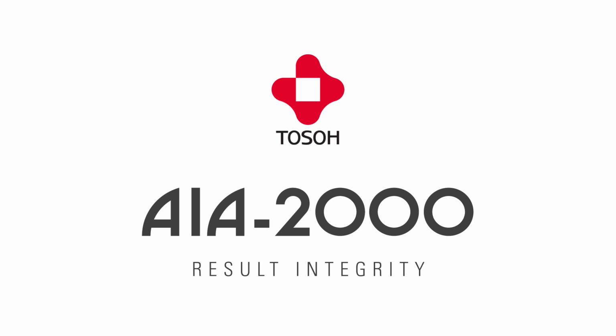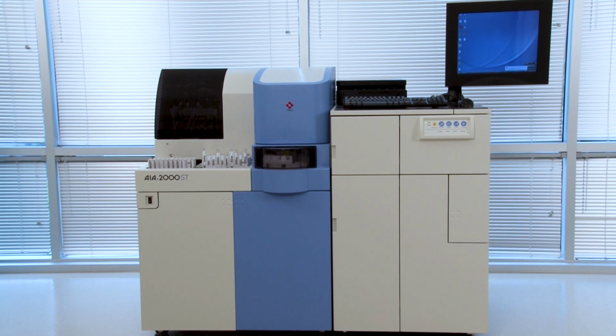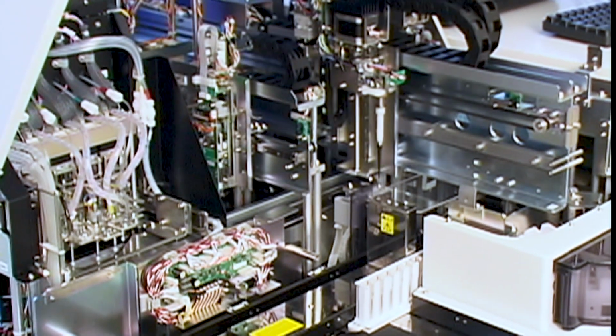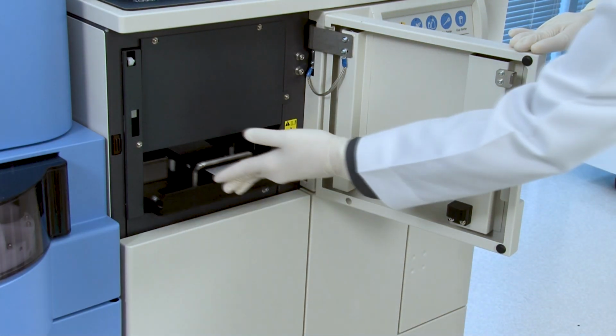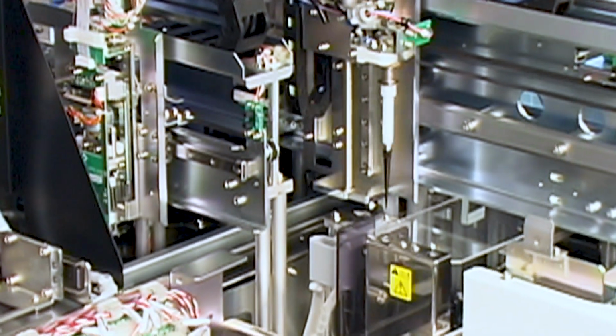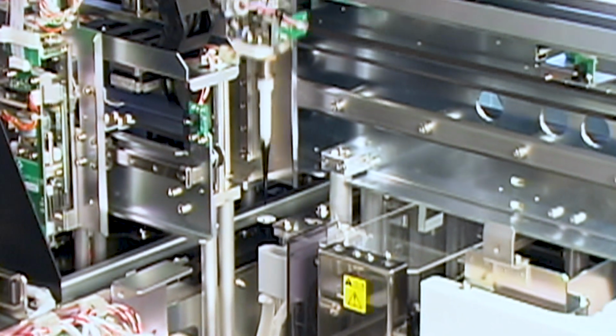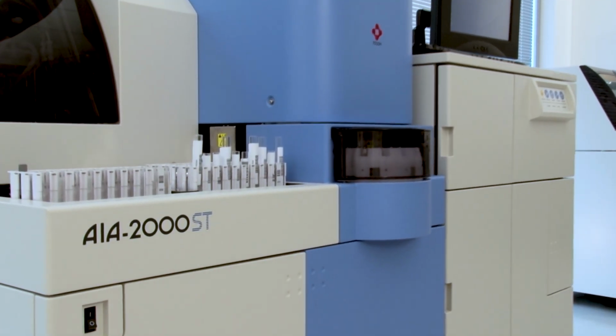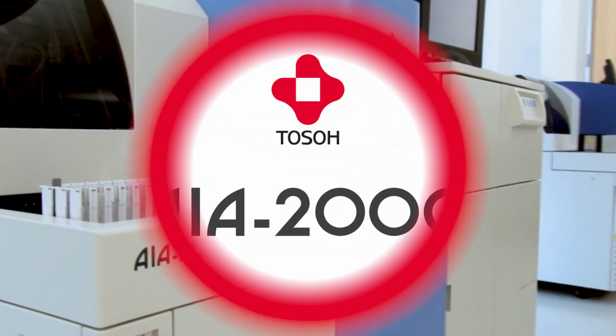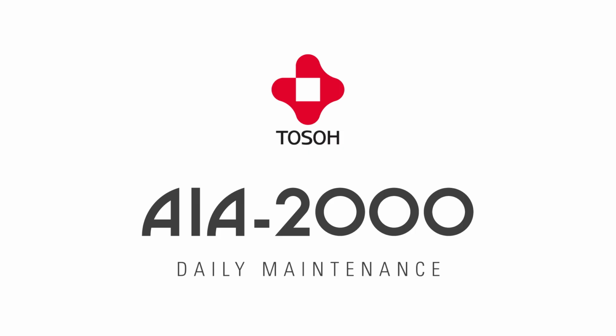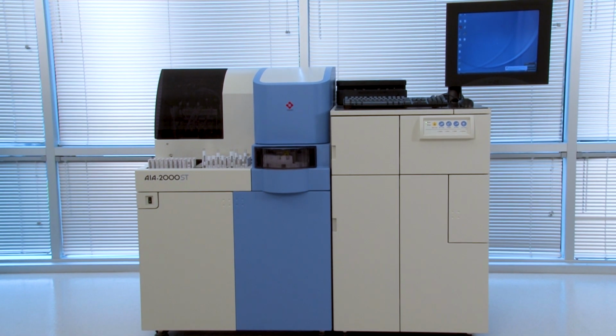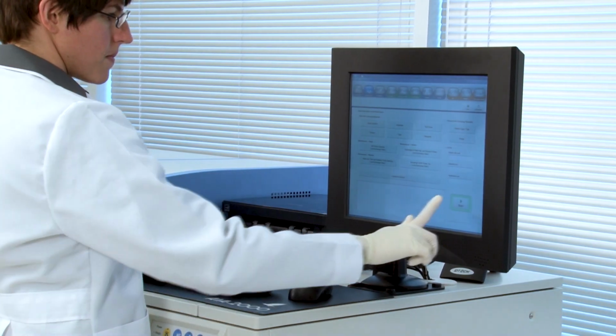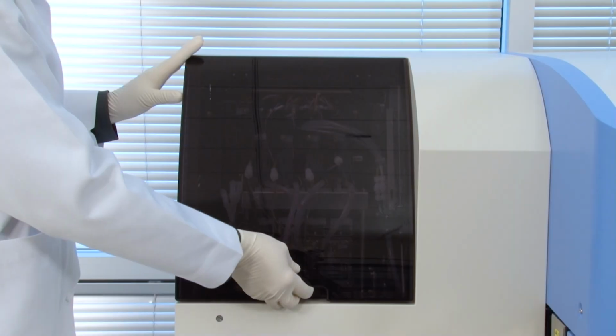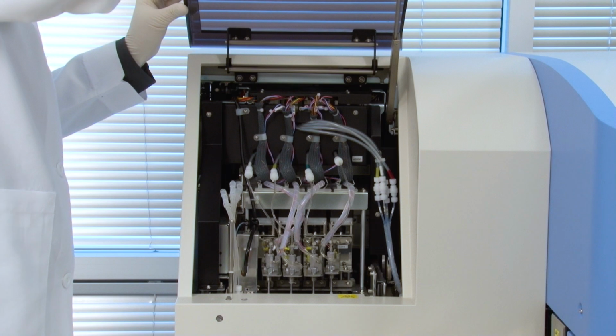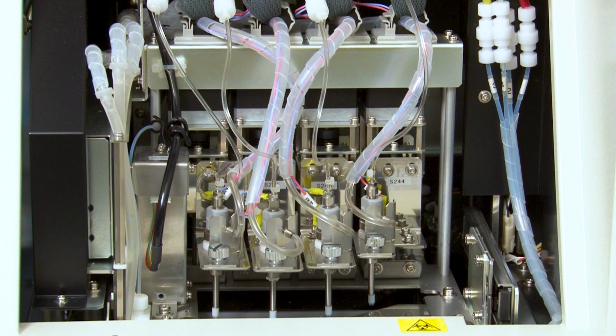To ensure the highest level of result integrity, the AIA 2000 features several built-in safeguards, including conductive disposable pipette tips for automated sample level sensing and elimination of carryover. The system also features TOSO's exclusive clot detection, which will detect a clot at the beginning of the sample processing and again during the wash phase. Daily maintenance on the AIA 2000 is totally automated and requires only 5 minutes per day at system startup. Weekly maintenance requires only a few minutes of operator time and involves a simple cleaning of the wash probe.